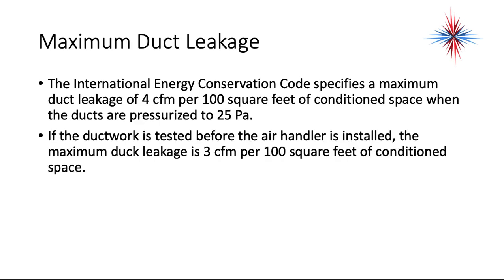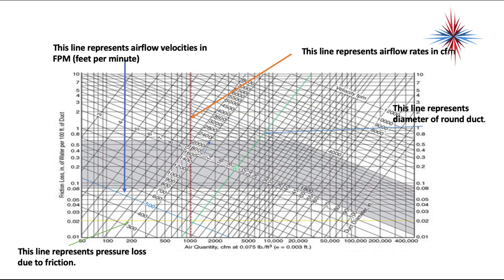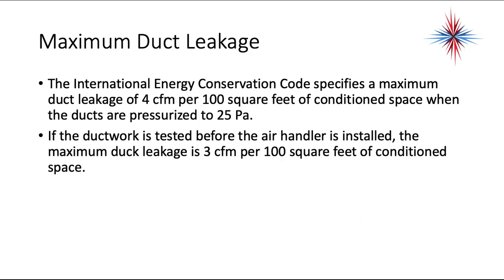We also need to discuss duct leakage. The International Energy Conservation Code specifies a maximum duct leakage of 4 CFM per 100 square feet of conditioned space when ducts are pressurized to 25 pascals. If ductwork is tested before the air handler is installed, the maximum is 3 CFM per 100 square feet. More and more, these tests are required to be performed by a third party. Learn to read the friction chart — there are many versions, including the ductulator wheel and electronic versions — and understand duct leakage requirements.